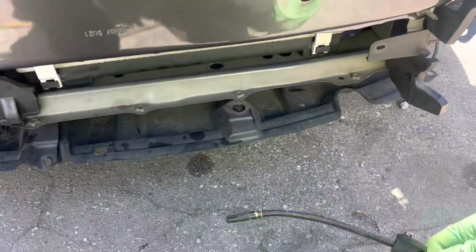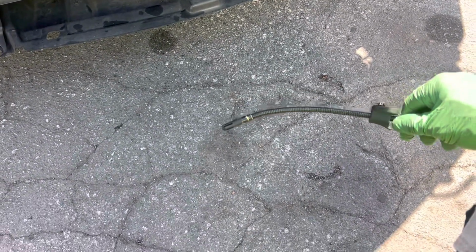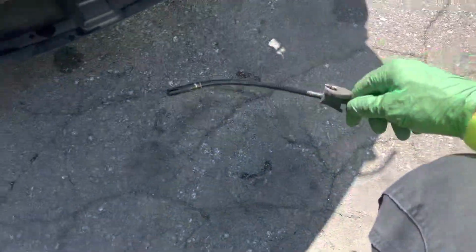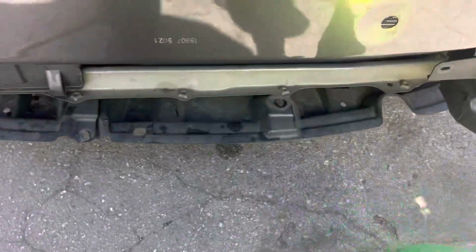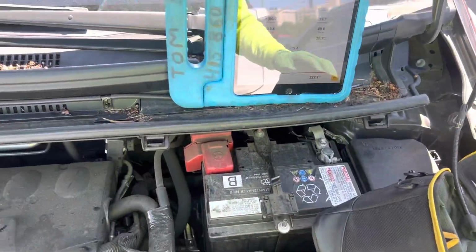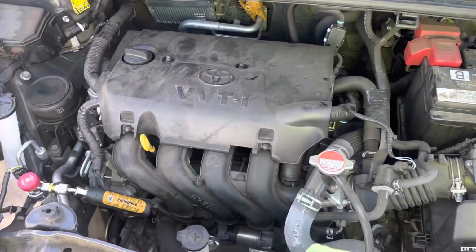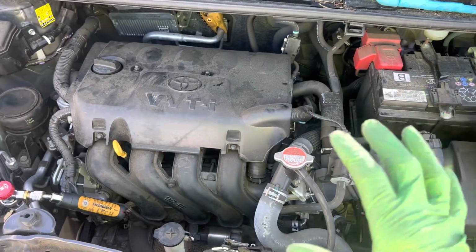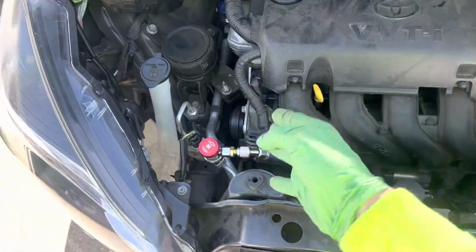But what you'll find on 95-degree days with no wind, if you take your thermometer and come down about the height of a condenser off the roadway, off a blacktop like a freeway or a roadway, you'll see it'll be about 110, 105 degrees, and that's what will be going up in your condenser. People don't think about that. So we have a system that, as long as he doesn't go anywhere really hot, the customer might not notice it. But this is the kind of thing that sets you up.